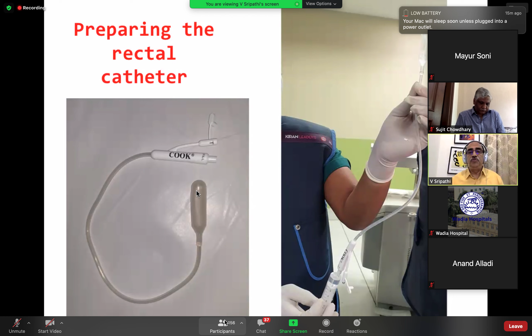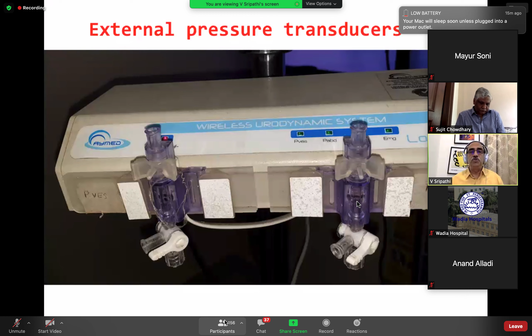There is a specific way in which you prepare this rectal catheter: you take out all the air bubbles, you fill it, and then you measure the pressure through this particular channel here. So these are the external pressure transducers. There are different machines; this is one machine that we use. We are not conducting a workshop, so I'm just taking the most important points and giving them to you. The external transducer should be at the level of the upper border of the symphysis pubis, and 0 centimeters of water is at this level. If you don't get this right, there will be an error in all subsequent measurements. So it's very important for you to do this.